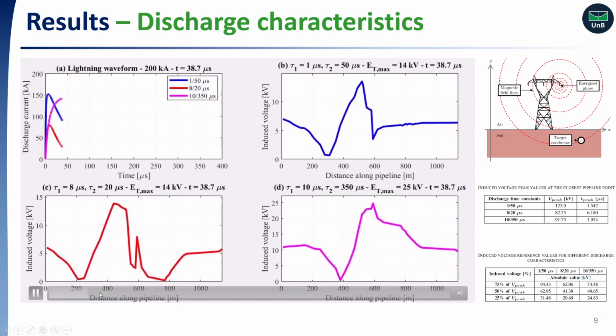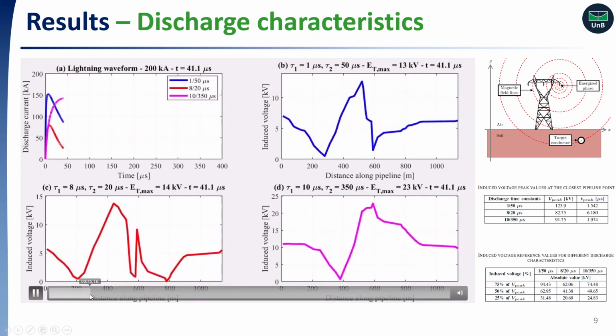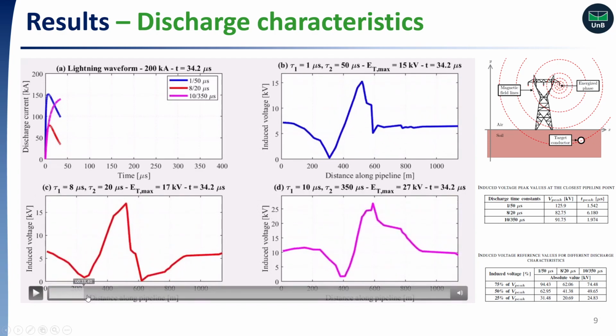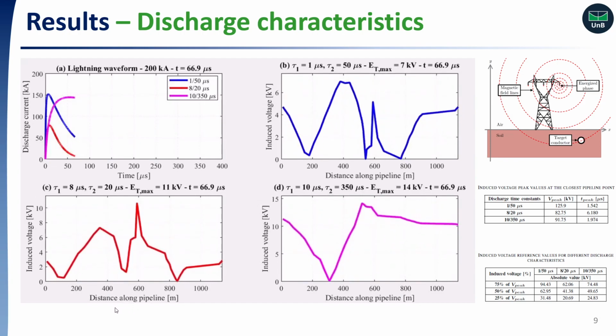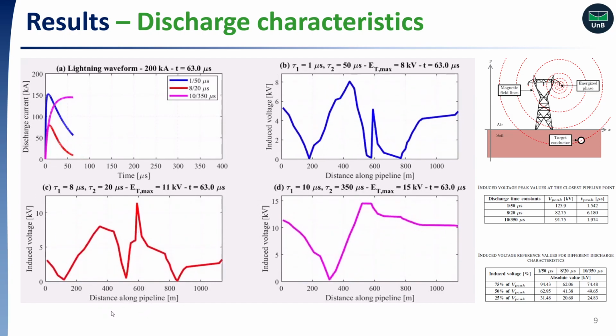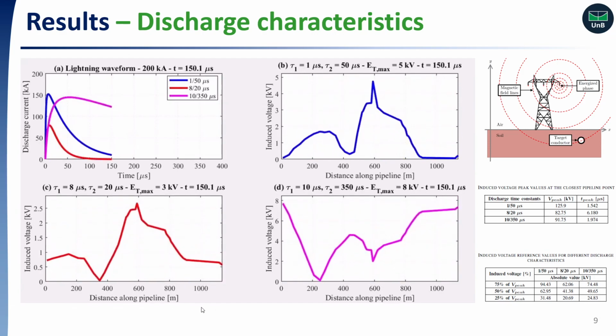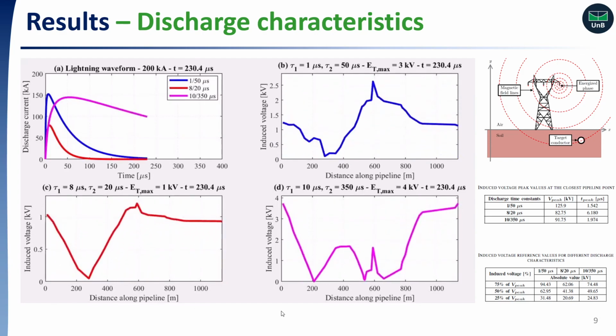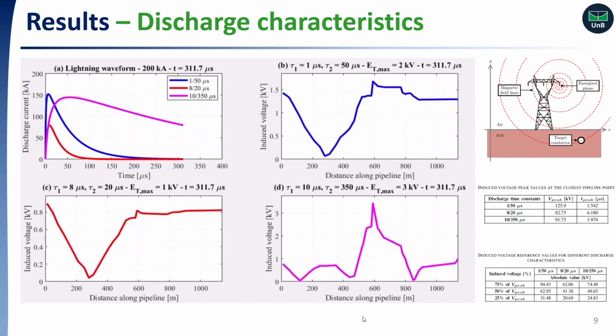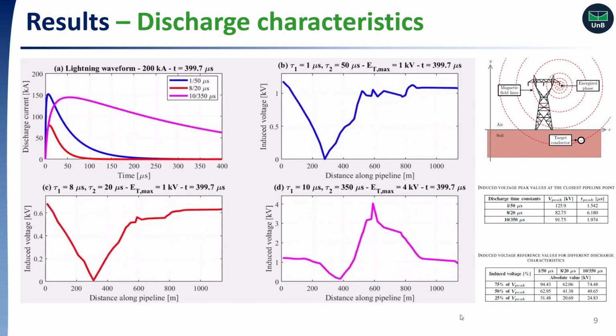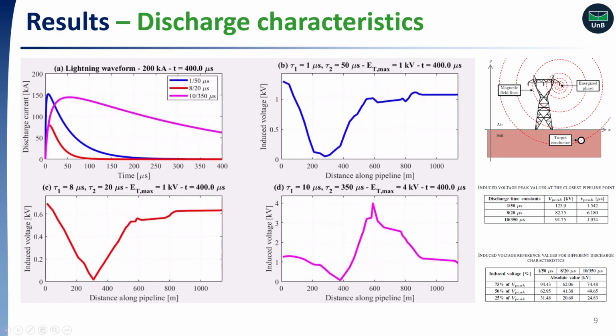Well, I will fast forward this now, and if I move this back and forth, we can clearly see the wave pattern and the propagation along the pipeline. So I will fast forward this so we get to the end of the simulation. And okay, we can see that the waves attenuate, and in the end we have some residual value here in the pipeline that will eventually fade.